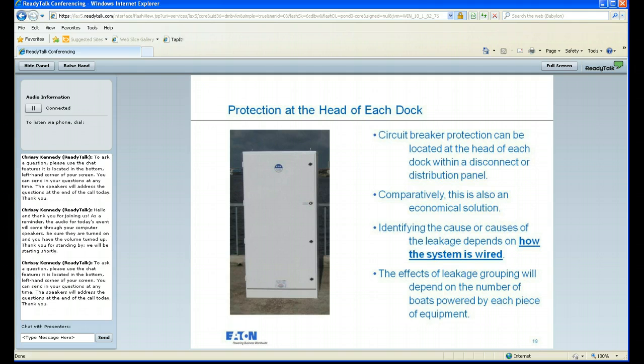The next place we'll look at protection is at the head of each dock. And again, as Gary pointed out, it needs to be protection where you have it on a lower voltage, be it 120/240 or 120/208. You're basically providing circuit breaker protection at the head of each dock using some sort of a disconnect or distribution panel. Again, this is a relatively economic solution compared to some others that are out in the market. Identifying the causes of the leakage often depends on how the system is wired, and we'll also go over the differences between identifying the culprits of leakage based on how the system's wired here in a minute.